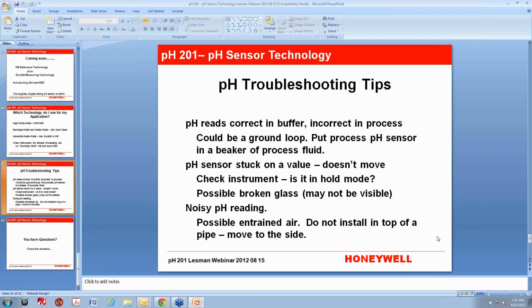So a lot of times you can have a pH sensor in your process, and say your process is 9 pH, but it's reading 11 pH. And you're like, well, that's no good. But you take it out and put it in a buffer, and it seems to read correctly. The test would be to pull a sample of your process and put the sensor in that beaker, a glass beaker or a plastic beaker, something that's insulated and isolated, and see if it reads the process correctly. If it does, what that means is there is a problem with the insulation. There is some voltage in there that doesn't belong, and it's upsetting the pH measurement.